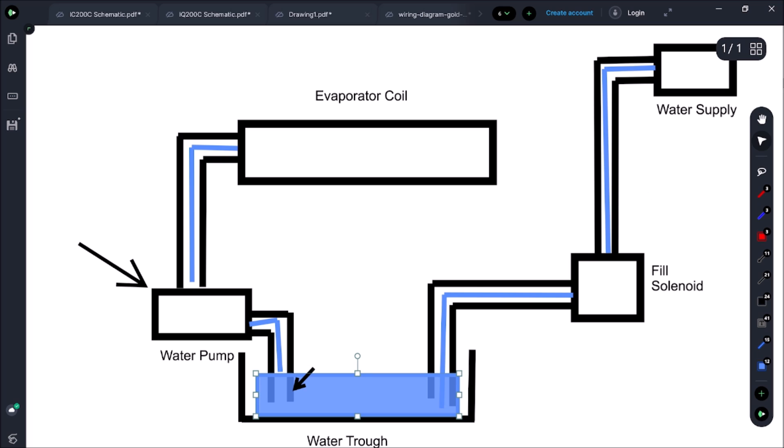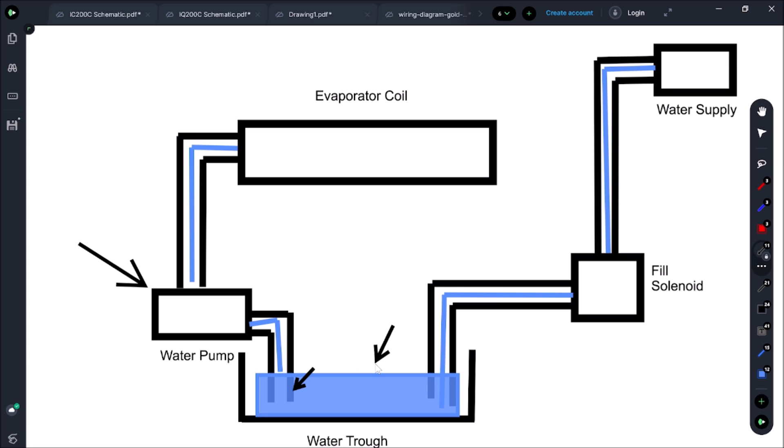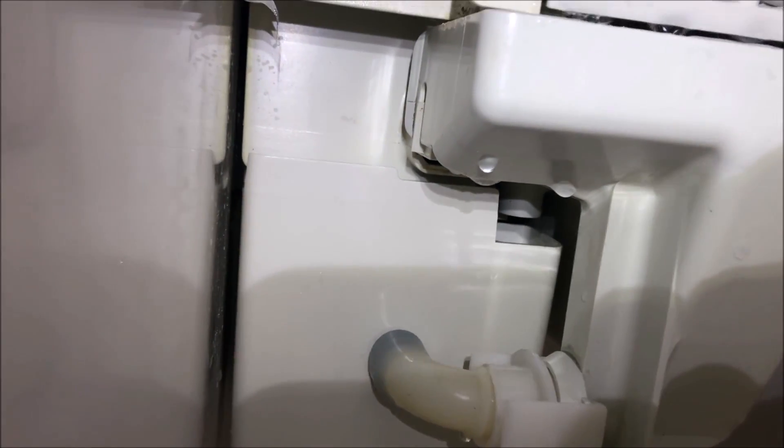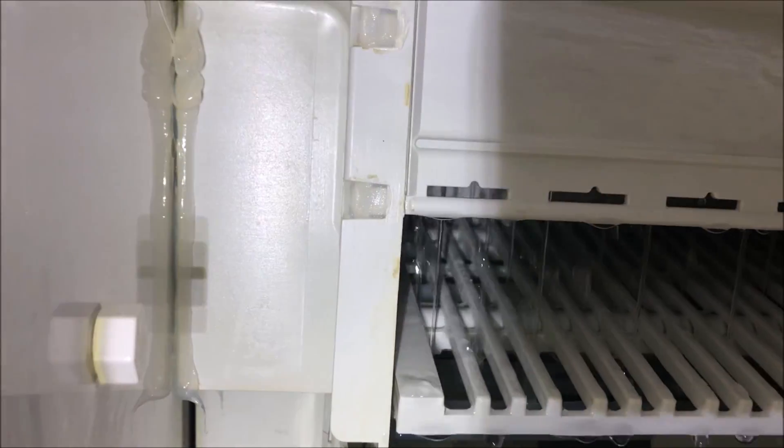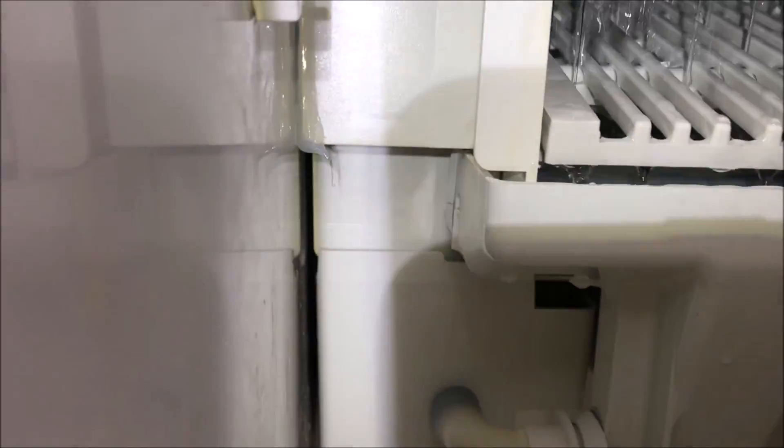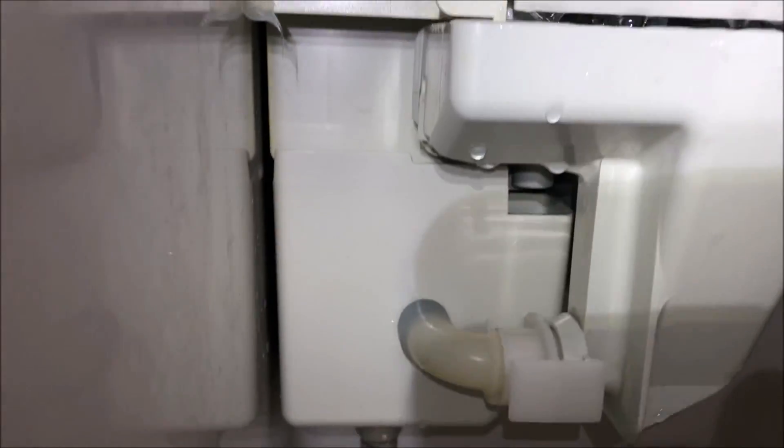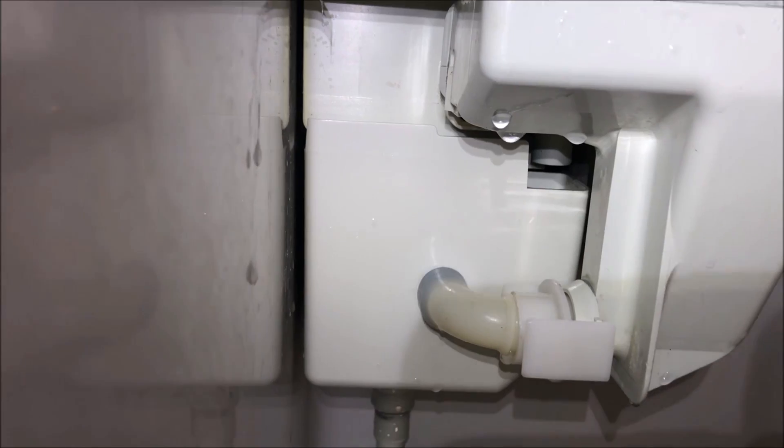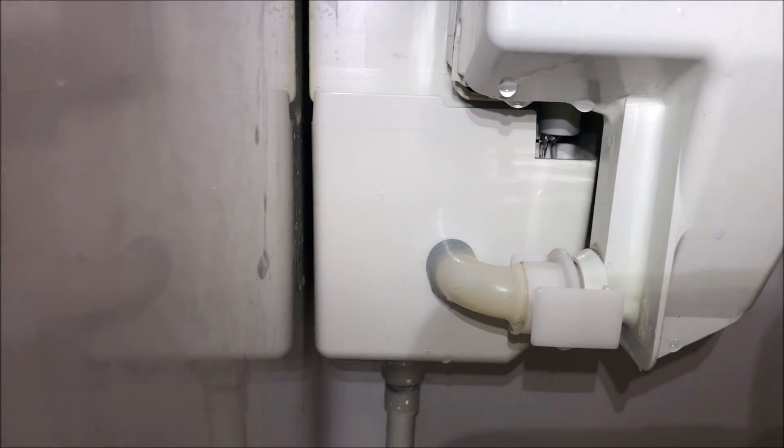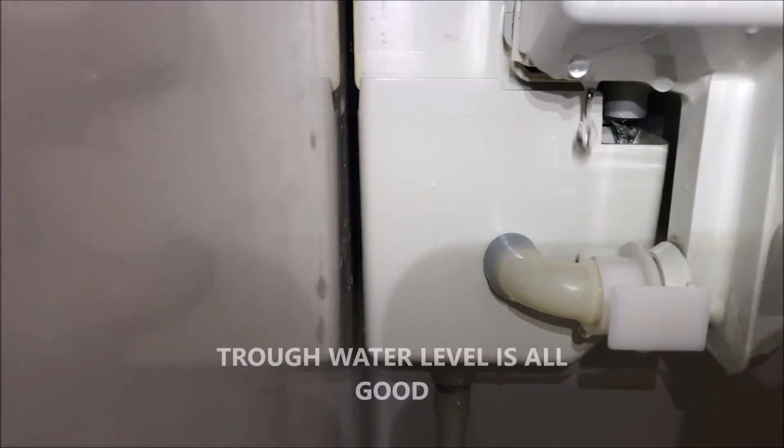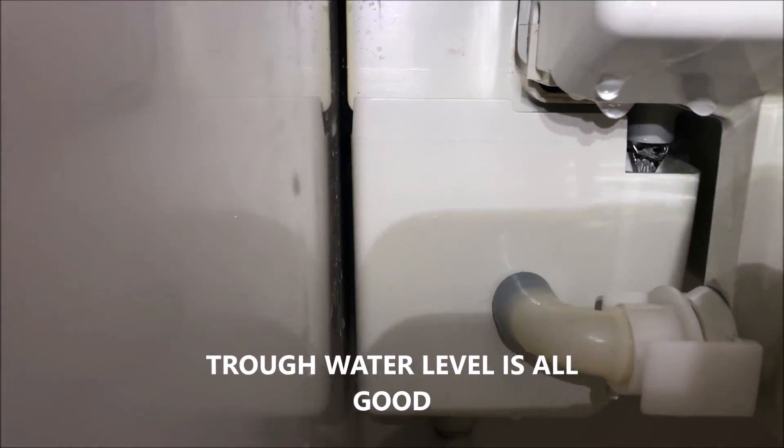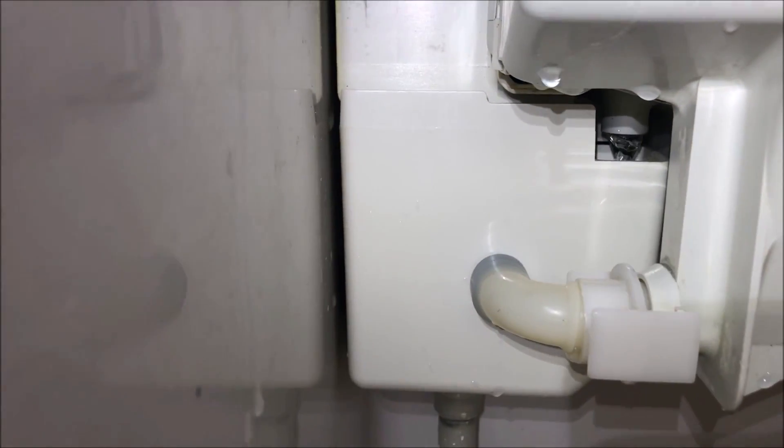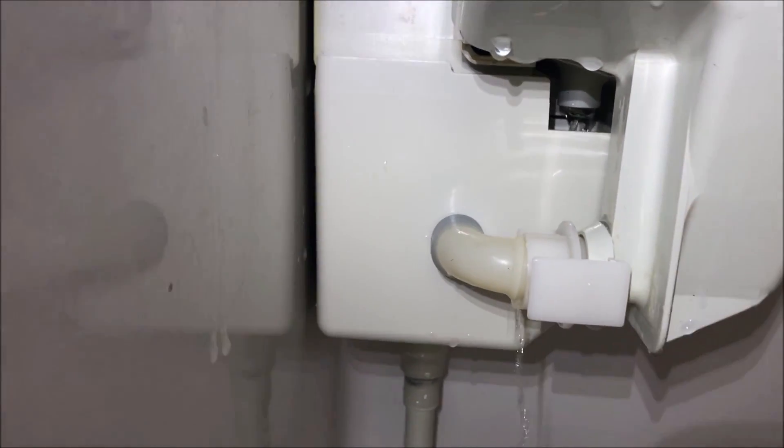What I'm gonna do is dump more water in here and I'm gonna see if it comes out of the overflow. If it comes out of the overflow within a couple seconds, the overflow will be somewhere right here. If it dumps out of this overflow, I know we have enough water in that trough. So let me go add just a little bit of water. Let's dump it in and let's watch our overflow. And see right there. That's telling me we have enough water in the trough. So that's telling me the pump's good and the solenoid's good.